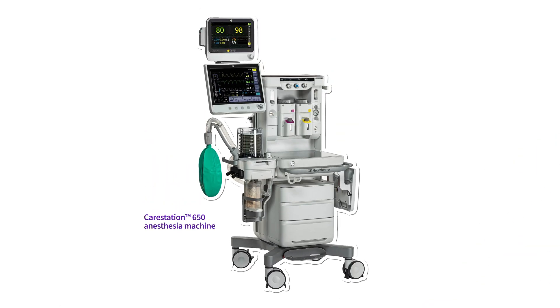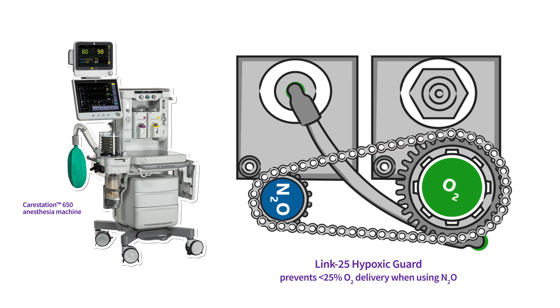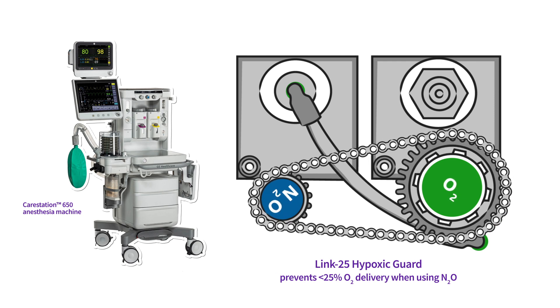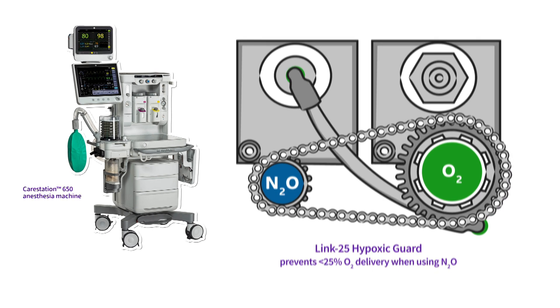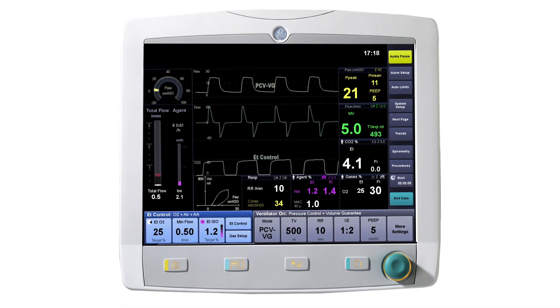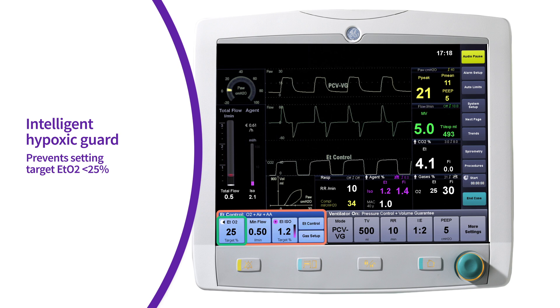With manually controlled circle anesthesia systems, there are conventional hypoxic guards that control the oxygen percentage in the fresh gas flow and not the circuit FiO2. This could result in hypoxic levels of inspired oxygen. GE Healthcare's Aisys CS2 end-tidal control contains an intelligent hypoxic guard, since the oxygen percentage is controlled at the patient level by automatically compensating for metabolic rate changes, ensuring targeted end-tidal values.